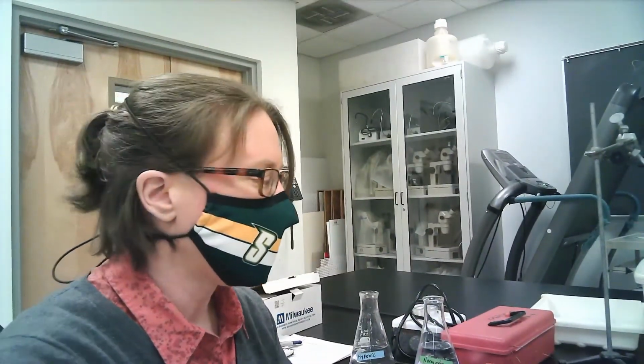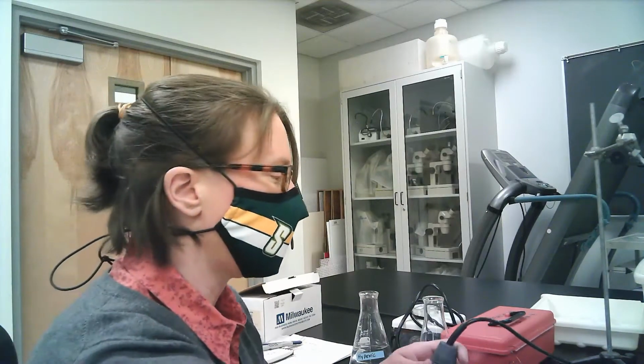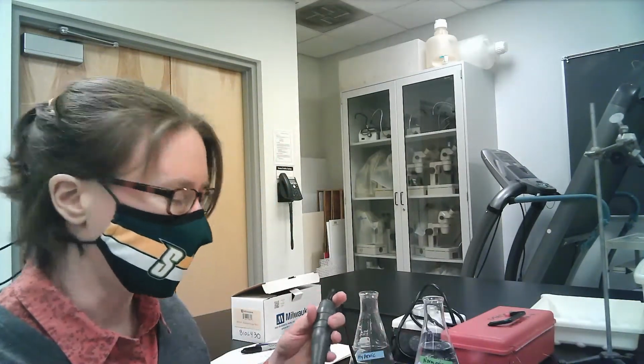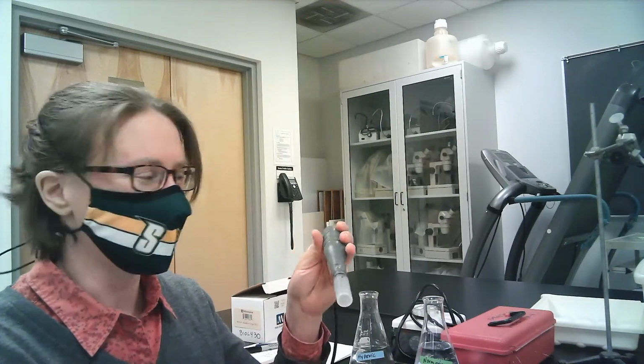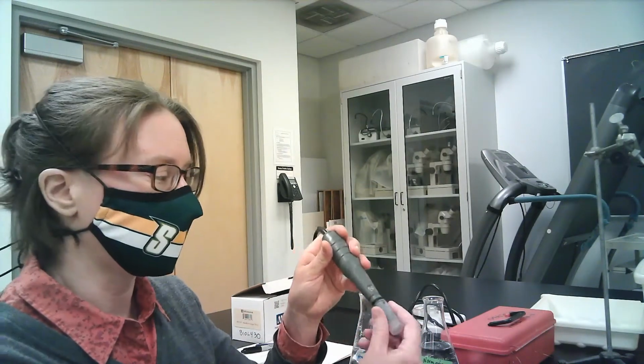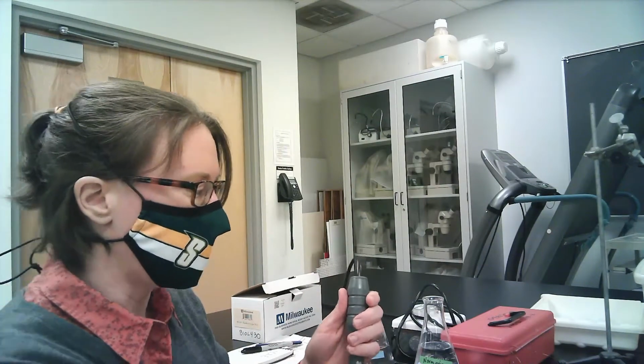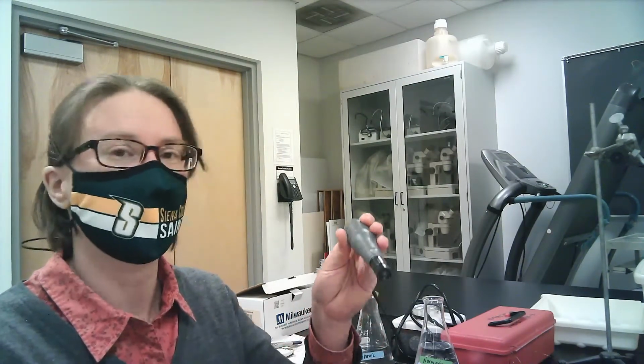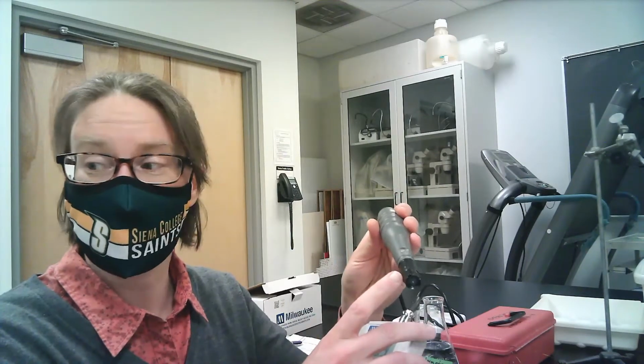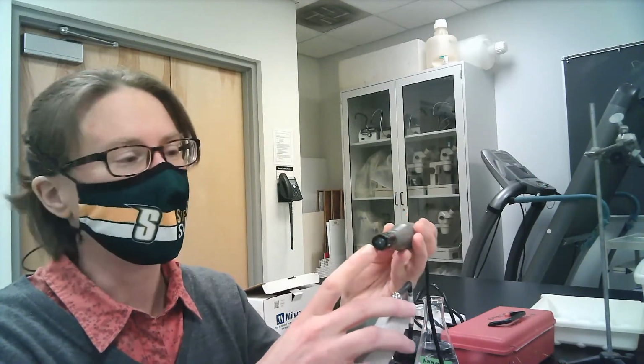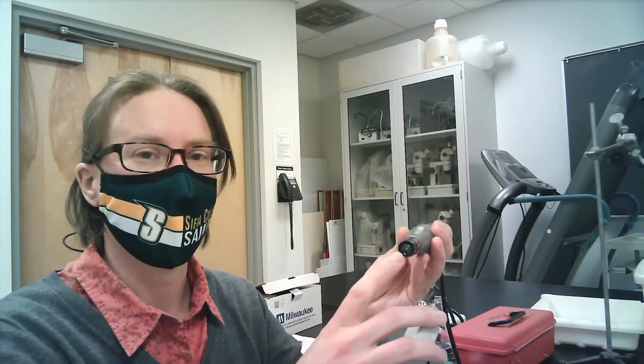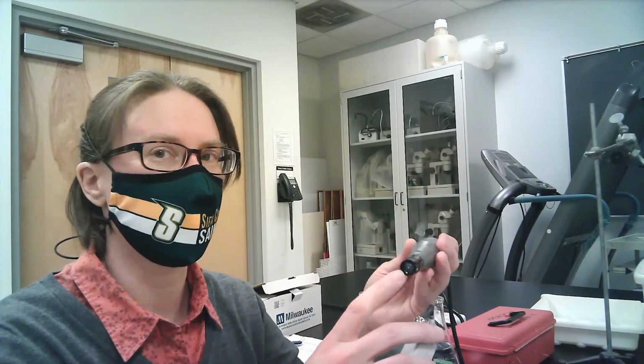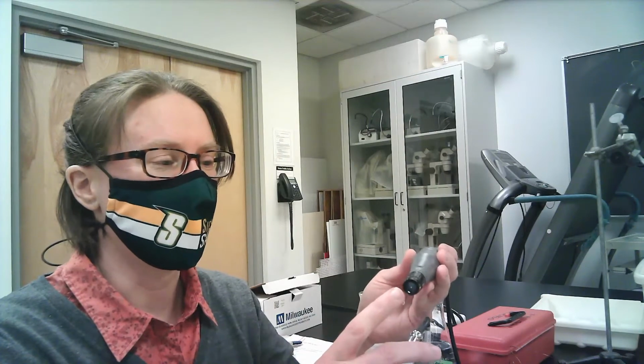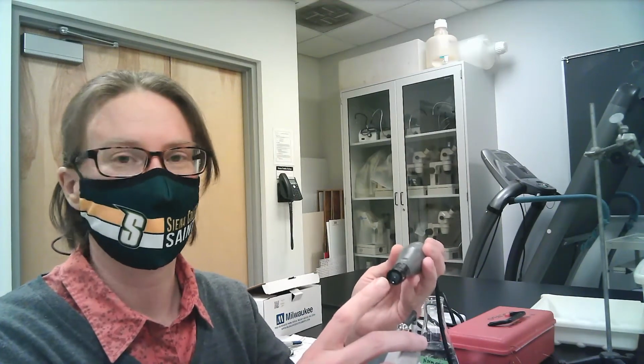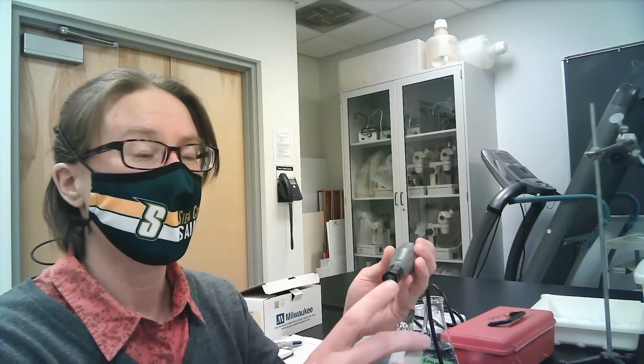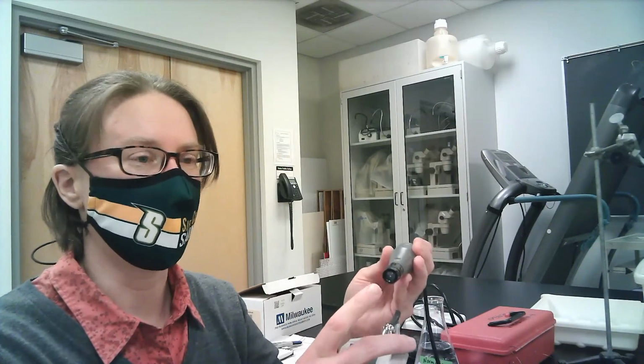Okay? And then when you are ready to use it to measure the oxygen concentration in your water, the first thing you need to do is remove the cap over the top of the electrode. Just for your reference, inside of here is a little chamber that's filled with salt water, and there's a little mesh membrane over that chamber that keeps the salt inside. That's what's actually going to be measuring your oxygen concentration. So try to avoid coming into contact with or damaging that little membrane.